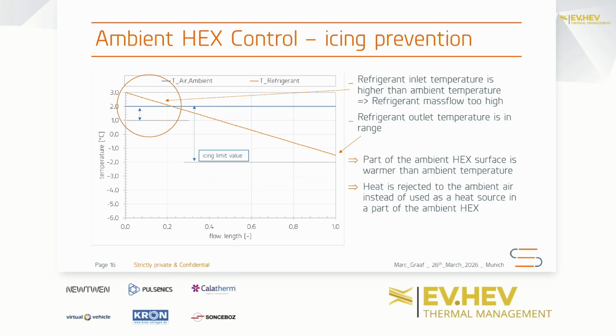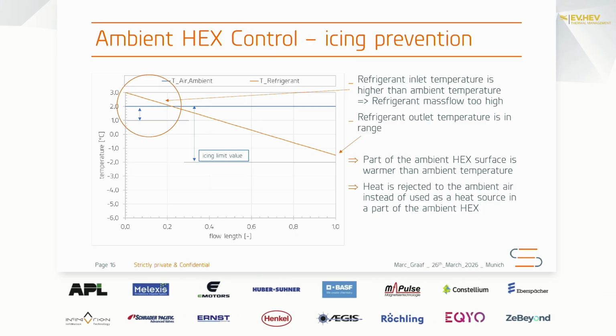if you control your system in the wrong way, you would get a situation like is shown here. So the blue line that you can see here is basically the ambient temperature. The compressor control basically controls the outlet pressure, which, if you don't have any superheat, gives the saturation temperature, which is, let's say, a maximum of 5 degrees below that ambient temperature. But if you have a very high mass flow, you also have a lot of pressure drop, and unfortunately the refrigerant has a temperature change that is based on a pressure change in the two-phase area. Those two physical conditions are connected.